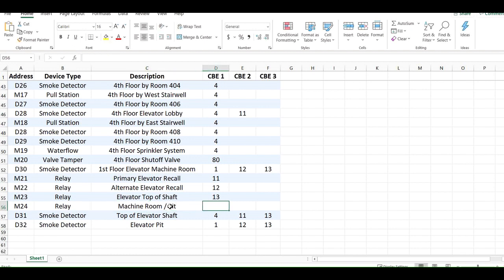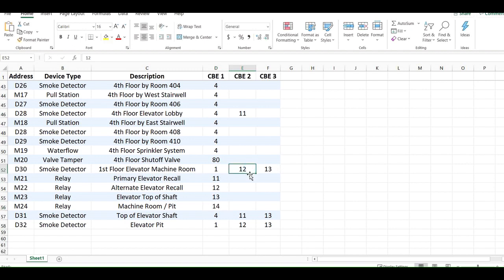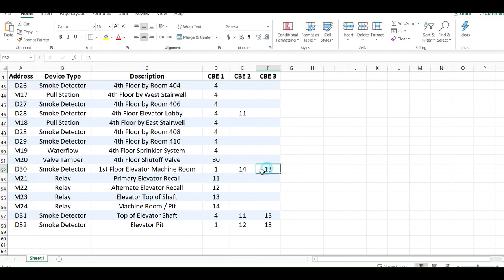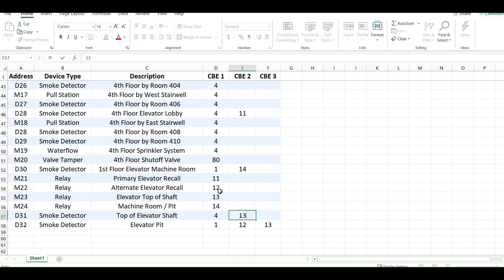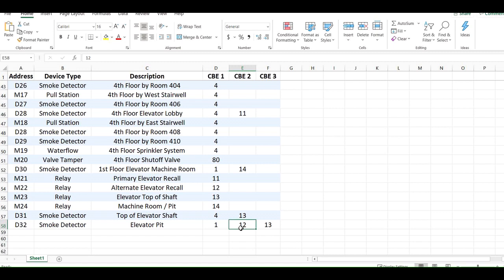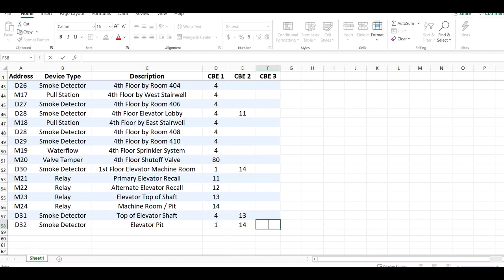That would be zone 14, and now you're just going to zone your smokes accordingly. So first floor machine room, instead of turning on 12 and 13, now it's just going to turn on 14 because machine room, the relay for that is 14. Top of shaft, instead of turning on 11, which was primary, and 13, it's just going to turn on 13 because that relay is 13. And then the pit is going to mimic the machine room, which is zone 14 only. I think that's straightforward enough. Hopefully that makes sense. Thank you.